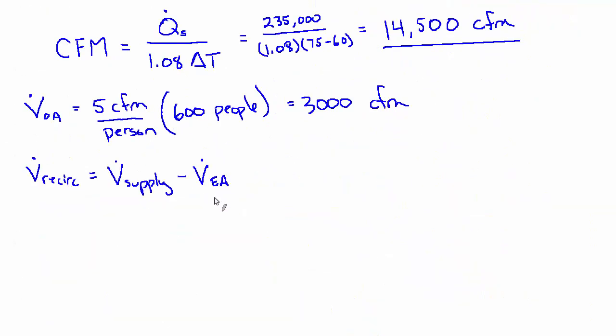And I wrote EA here, but this could also be OA. I think I will change that. They're the same volume. They're both 3,000, so I'd get away with it. But let's be clear. So 14,500, I'm skipping units here, minus 3,000 equals 11,500 CFM.